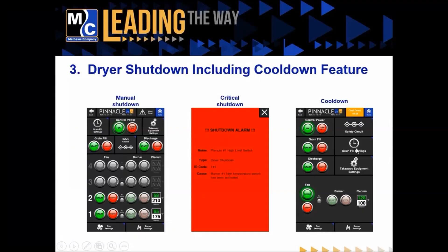So a couple takeaways from this segment. There's three different types of alarms. Warning alarms are yellow and will not shut you down. Cool down alarms are orange and are a delayed shutdown. And critical alarms are red and they'll shut down everything immediately. The cool down can be canceled if desired. And one thing I forgot to mention is that the timer is adjustable.